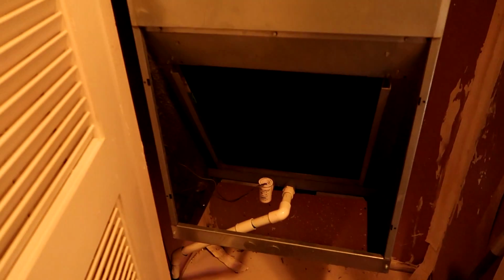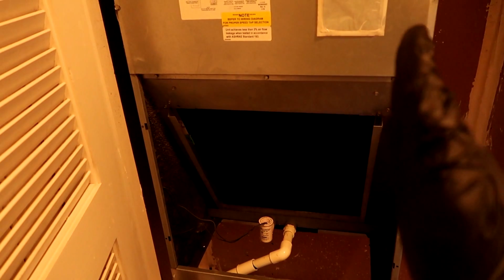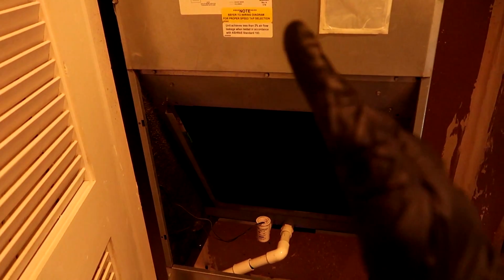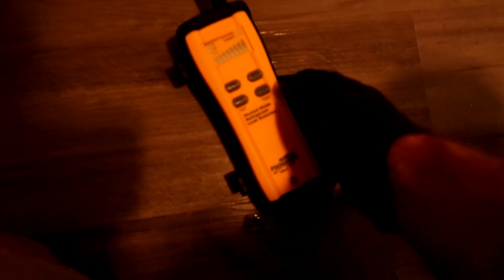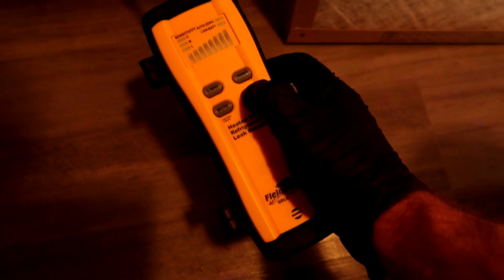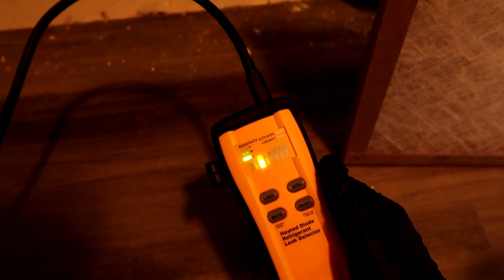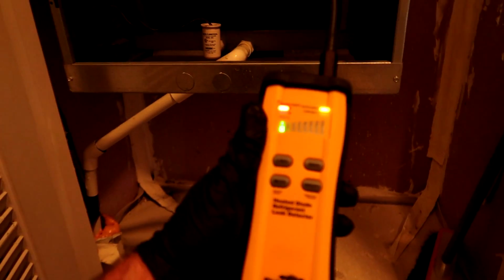You can tell when someone puts a filter in when you're down there doing the charge, because you'll see the suction pressure drop. All right, grab the leak detector. You let it warm up. These things got to warm up. Once it starts giving me the beepy beep, I'll be back. All right, here we go.